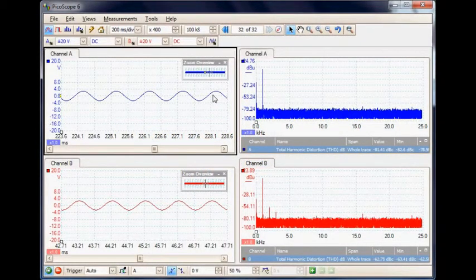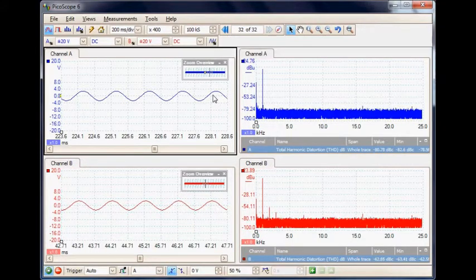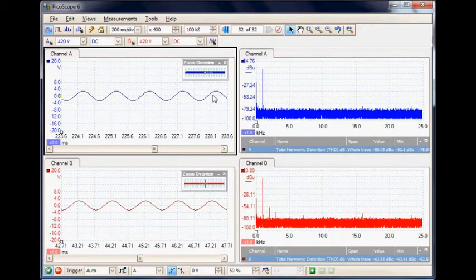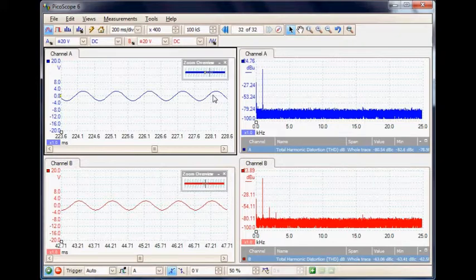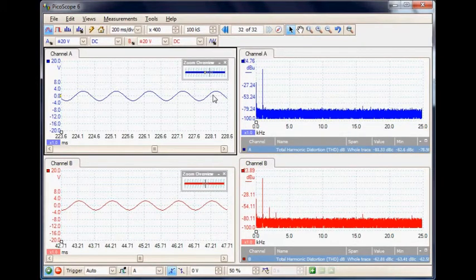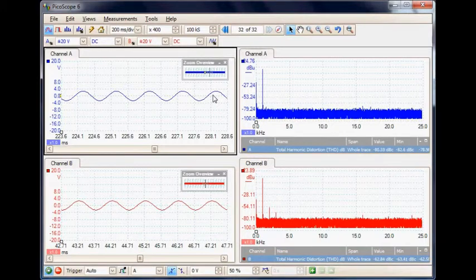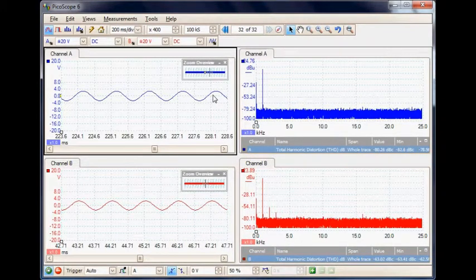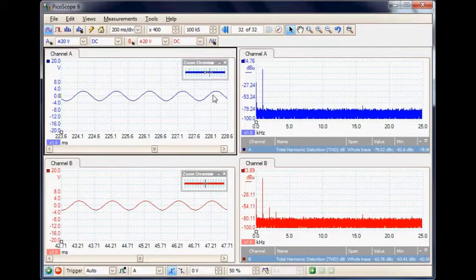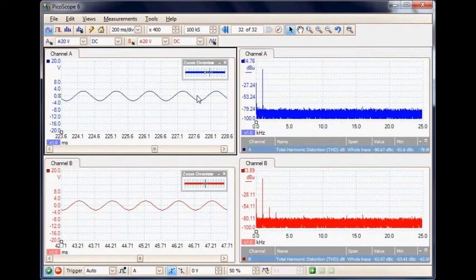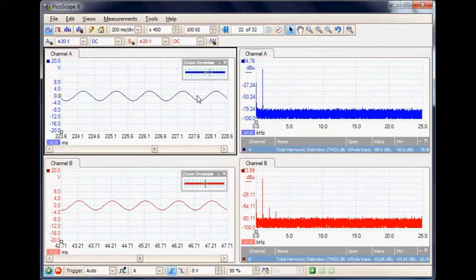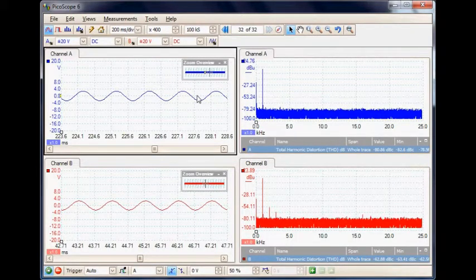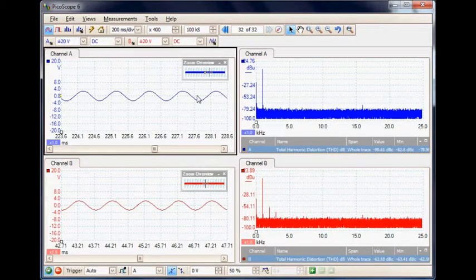The 4262 oscilloscope is a dual channel high vertical accuracy measurement instrument. It has 16-bit digitizers which give very high accuracy in the vertical plane, making it very useful for audio measurements. It still has a lot of general-purpose diagnostic tools which make it useful for fault finding in audio systems.